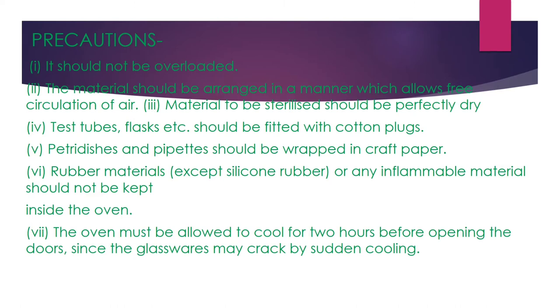Test tubes and flasks should be fitted with cotton plugs. Petri dishes and pipettes should be wrapped in craft paper. Rubber materials should not be used except silicone rubber. Any inflammable material should not be kept inside the oven. The oven must be allowed to cool for two hours before opening the doors, as glassware may crack from sudden cooling.